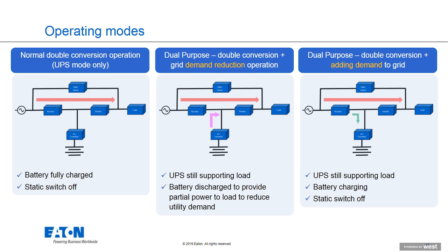Okay. In a dual purpose or an energy-aware application, we'd be looking at operating in double conversion plus some demand reduction. So how do we reduce the amount of power that we pull out of the utility company's source on the left of that picture? Well, if we discharge the battery, see the pink arrow in the middle there, we discharge the battery while we continue to remain connected to the incoming utility source, we can discharge that battery and reduce the amount of power that we pull in from the utility company.